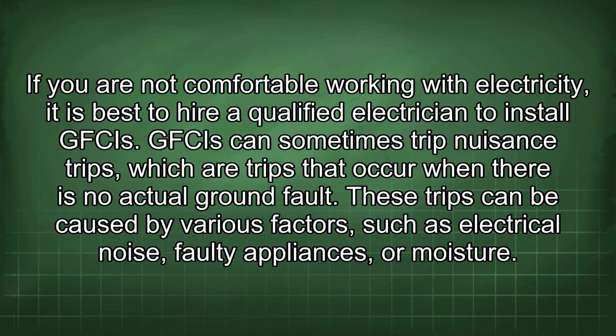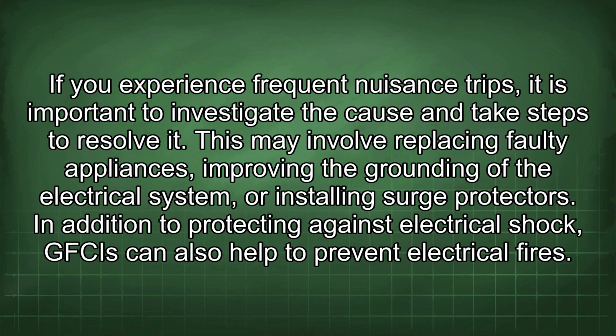GFCIs can sometimes have nuisance trips, which are trips that occur when there is no actual ground fault. These trips can be caused by various factors such as electrical noise, faulty appliances, or moisture. If you experience frequent nuisance trips, it is important to investigate the cause and take steps to resolve it. This may involve replacing faulty appliances, improving the grounding of the electrical system, or installing surge protectors.